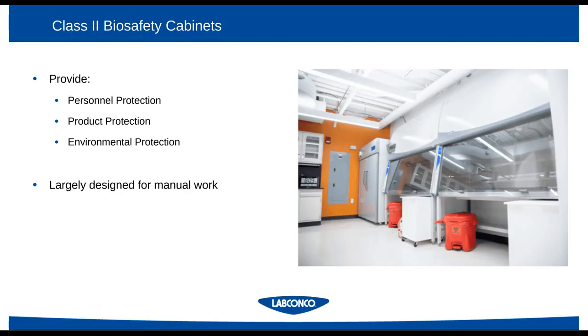Now, looking at standard Class II biosafety cabinets, these have been around for 50 some odd years. We know they provide personnel and product protection, and then, of course, environmental protection by not letting any biohazardous materials back into the laboratory. And really, Class II BSCs are designed for manual work. So they're designed to be regularly used by a human inside the hood and to handle things like cell culture flasks, reagent bottles, and other things that are smaller in size.